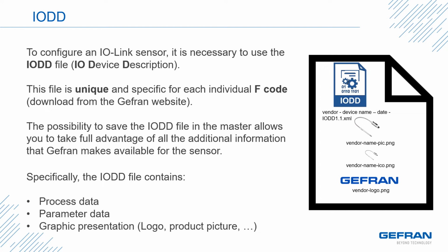This is one of the features that allows any sensor that doesn't match the description in this file to be indicated by an error so that the system is alerted that the wrong sensor is installed in this port of the master. The file contains process data, parameter data, a graphic presentation of the manufacturer, for instance, the logo or a picture. It makes it easy for programming the system and making sure that the correct sensor is installed and identified properly.